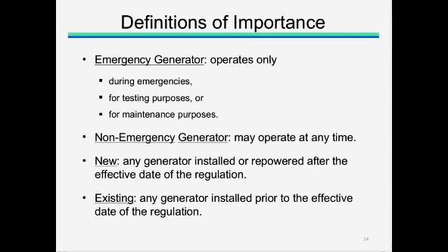As the two individual definitions on the previous slide suggest, an emergency generator can only operate during emergencies, but it can also operate for testing and maintenance purposes as well. A non-emergency generator may operate at any time, including emergencies, testing and maintenance, as well as any other time it wishes. Different requirements of the model rule will apply to different generators depending on when they are installed, which is why definitions of new or existing have been included in the model rule. These terms are used to define a generator which is installed or repowered after the effective date of the regulation, once a state adopts the model rule, of course, as new. A generator which is installed prior to the effective date of the regulation would be classified as existing.